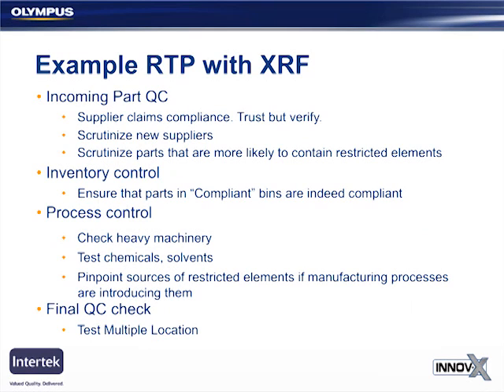So here are a few examples of places where XRF might fit into a reasonable testing program. With incoming part QC, you specify ordering compliant parts from your vendors, but for new suppliers or for parts that contain materials that have historically been more likely to contain restricted elements, you may want to scrutinize those more closely. XRF is useful for inventory control. If you're ordering similar parts that are both compliant and non-compliant, you can make sure that they've been sorted appropriately. This is mainly of concern if you're a manufacturer who's operating compliant and non-compliant manufacturing streams.